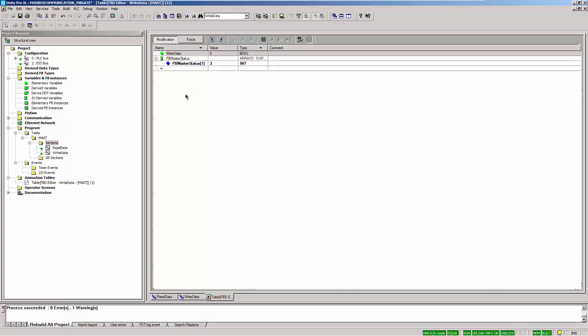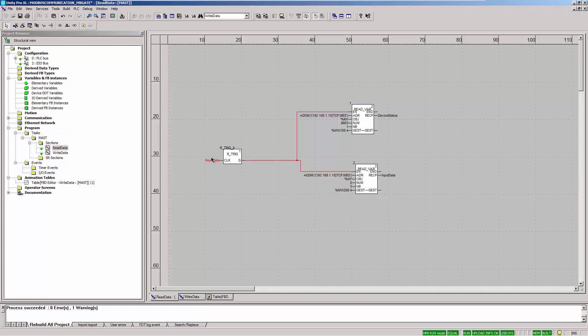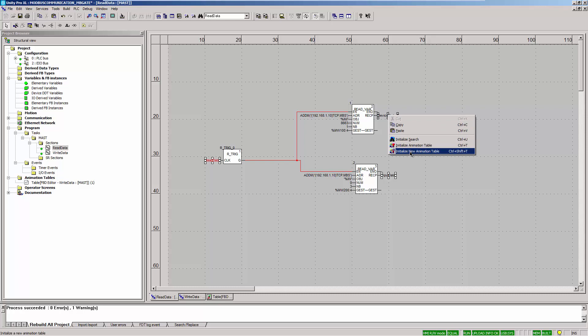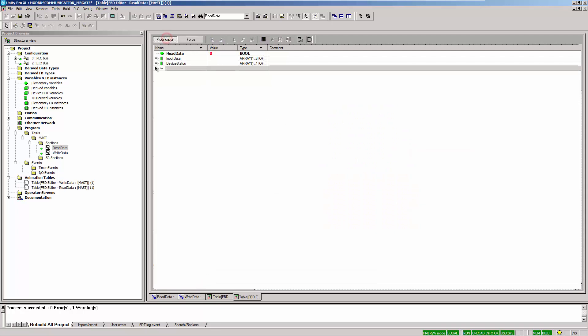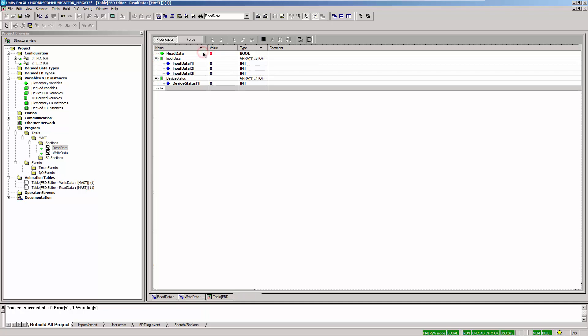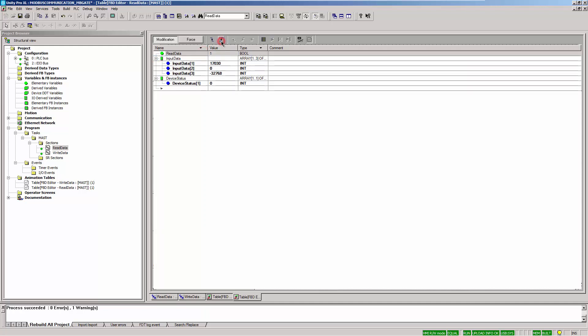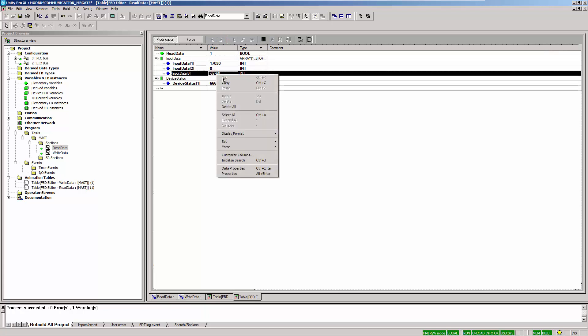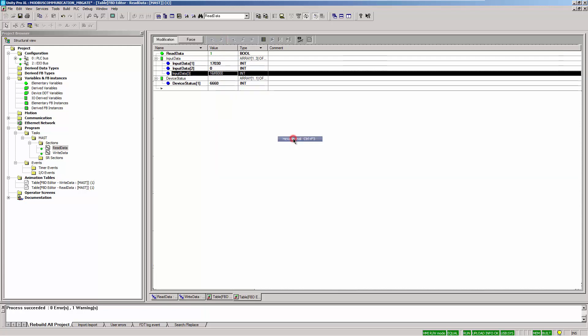Next, the status information and the input data are read out. Change to the corresponding function block diagram. Select the input variable of the R_TRIG function block and the two variables that contain the data. Initialize a new animation table by right-clicking on one of the selected parameters and choosing the corresponding option in the context menu. Reading is executed as soon as the input variable is set to 1. Change the display format of the last register of the input data and the status information register to hex to better interpret the data.